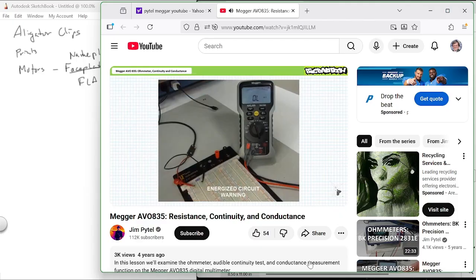Lastly, I must remind you that resistance, continuity, and conductance measurements must be taken on a de-energized circuit. In the event the Megger AVO 835 detects a live circuit, the instrument will sound an audible pulse beep and flash voltage over limit on the display. This audible warning prevents an operator from damaging the instrument, the circuit, or themselves in the case of an errant energized circuit.